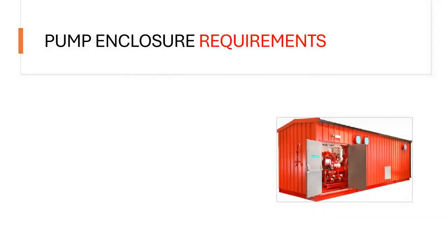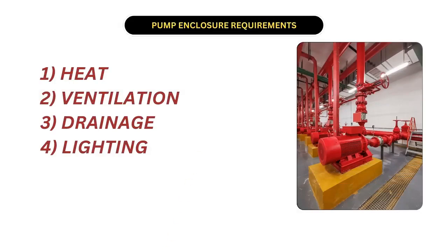Requirements play a critical role in ensuring the proper operation and longevity of the fire pump systems. Some of the most important requirements to be considered as per NFPA 20 are heat, ventilation, drainage and lighting. These are the most important parameters or factors that have to be considered whenever we are going to consider any fire pump room or fire pump enclosure.